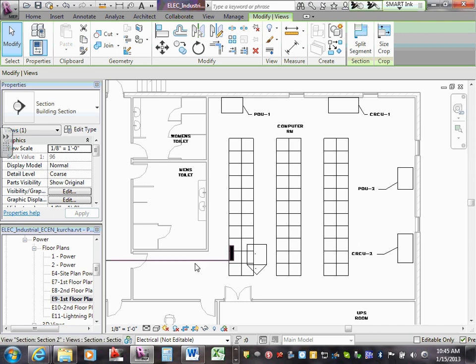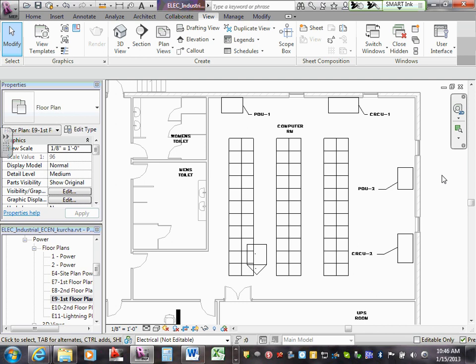Typically, when we're designing a computer room or a clean room like this, we're going to use a Vesda air sampling system, and that's a pipe system. And all it does is run a pipe down underneath the floor, and it's got air sampling pipes in it that are constantly drawing air. You're using the same spacing on your sampling pipes that you use for a smoke detector, depending on the air exchange. So we have that information. We're going to assume that it's 9 feet on center. So you're going to start out here with your Vesda panel. Your first pipe is going to come down and come over. You can T-tap off the pipe.